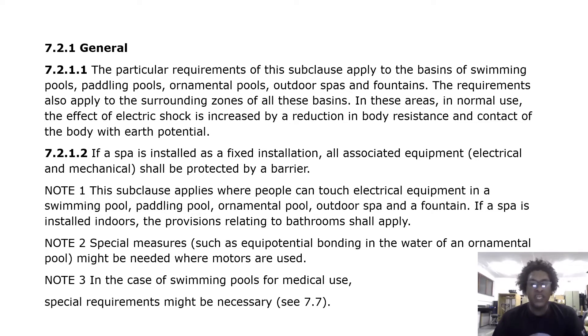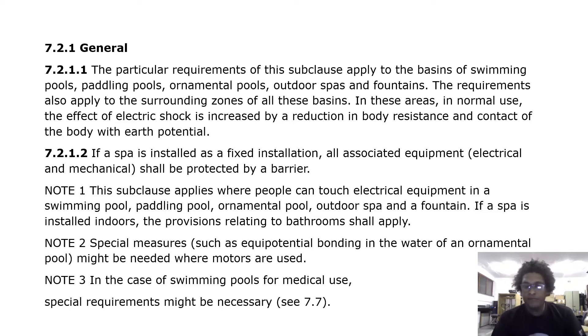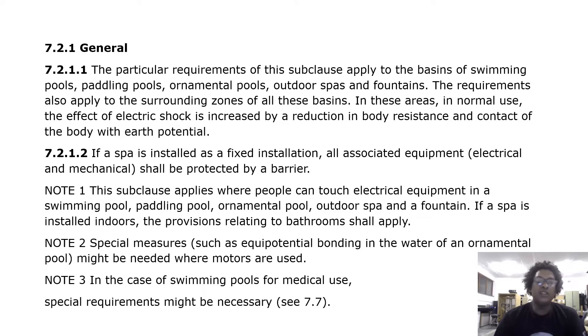If a spa is installed as a fixed installation, all associated equipment, electrical and mechanical, shall be protected by a barrier. Note 1: this sub-clause applies where people can touch electrical equipment in a swimming pool, paddling pool, ornamental pool, outdoor spa and fountain. If a spa is installed indoors, the provisions relating to bathrooms shall apply. Note 2: special measures such as equipotential bonding in the water of an ornamental pool might be needed where motors are used. Note 3: for swimming pools for medical use, special requirements might be necessary — see Section 7.7, medical installations.